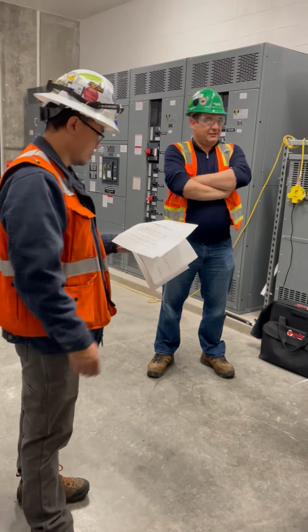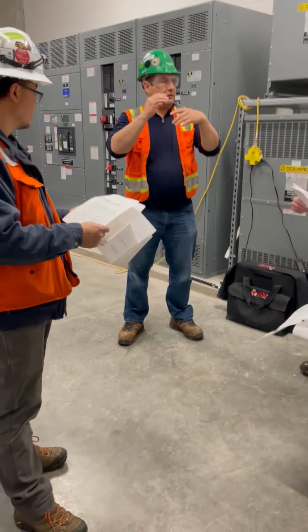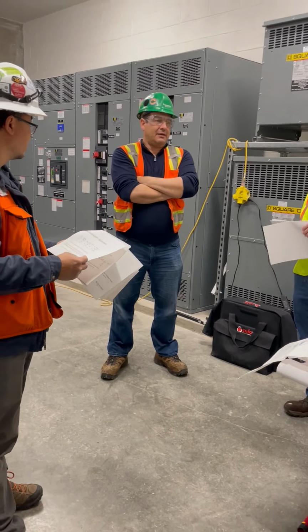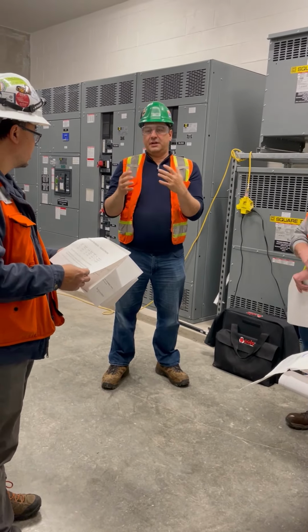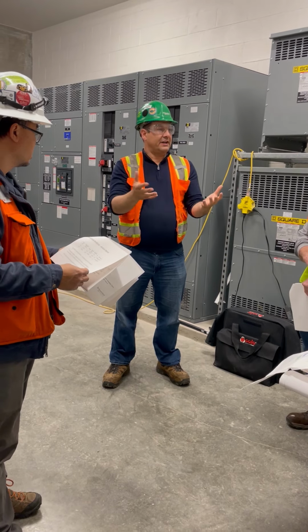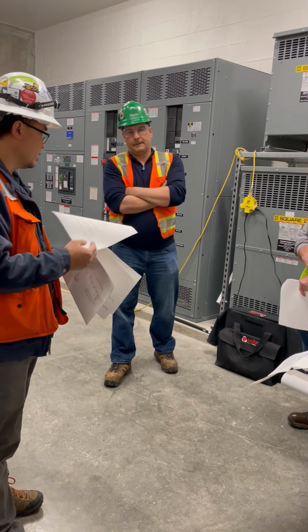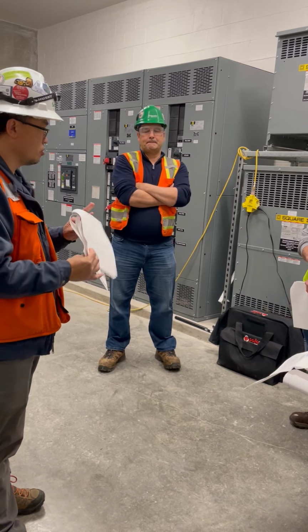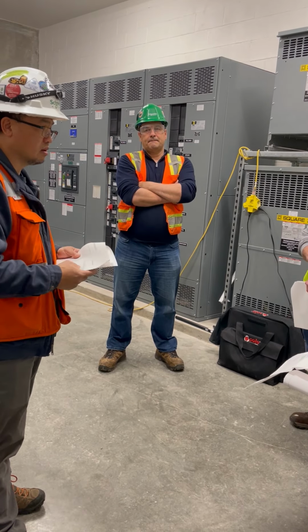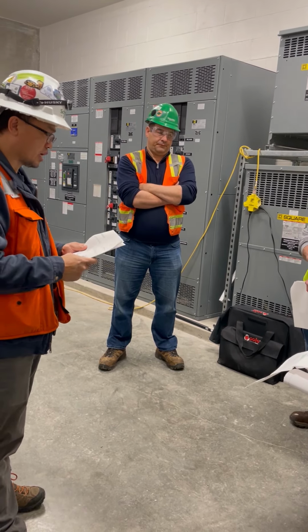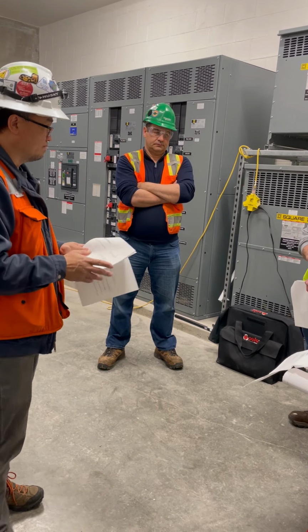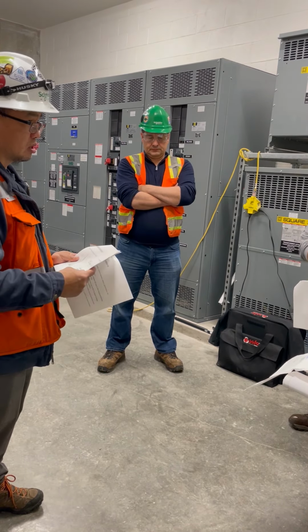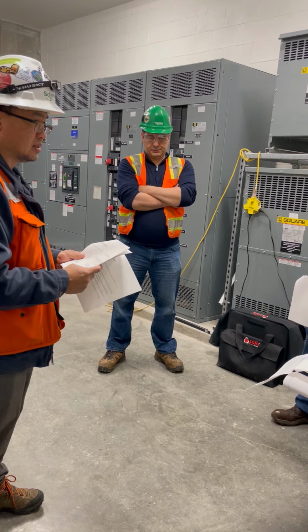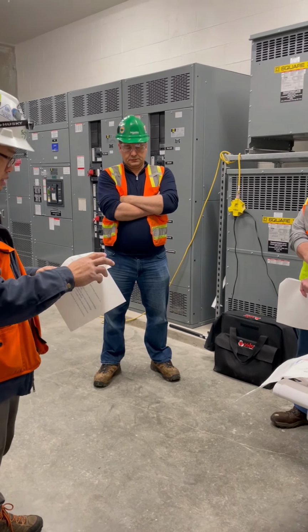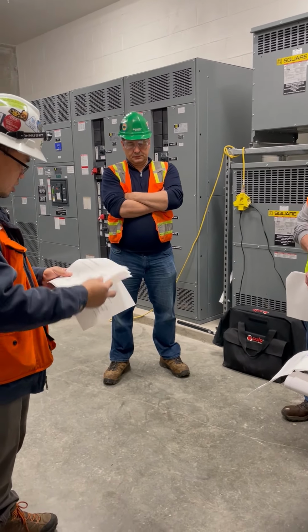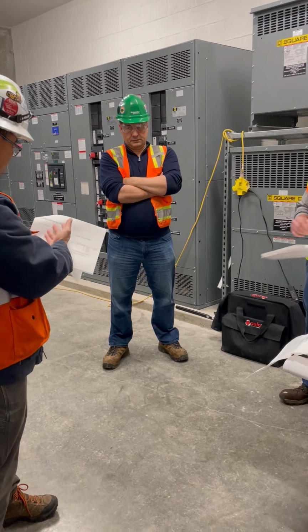So that's why rating the devices is really important in the future if you add loads. But if you're adding panels, anytime things are happening, that study will have to be revised. If you're adding any additional stuff, if you're putting in a generator or adding any big loads that can contribute to changing the available fault current, we really need to analyze the system to meet code. Of course, this is where I was talking about coordination studies.